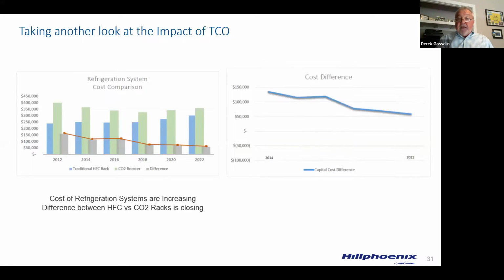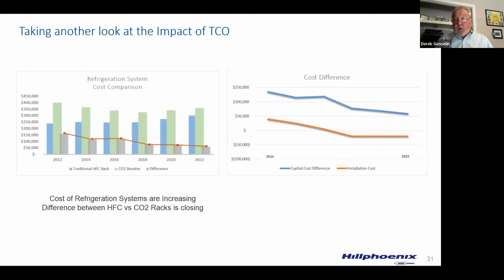So how do we take advantage and understand if our costs are coming down compared to our baseline? We understand that refrigeration installation is going to be lower because we're going to use less refrigerant at a lower price point. We're going to be able to save on the install by having smaller line sizes, which leads to lower labor installation and so forth. That can be valued, that can be calculated.